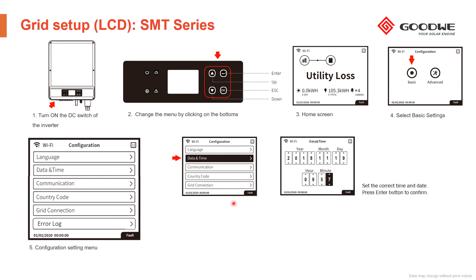By means of up and down buttons and enter and escape buttons, you can confirm and set data like language, the date, country code the same way. If you don't find your country, you can always set up the default 50 Hertz or 60 Hertz grid, depending on the region. And in advance, as we have seen, a power limit or grid type, delta and star.